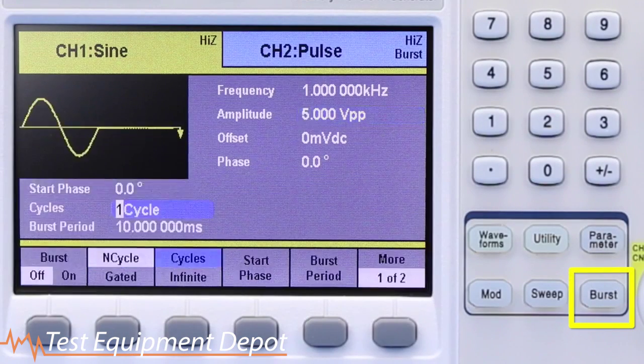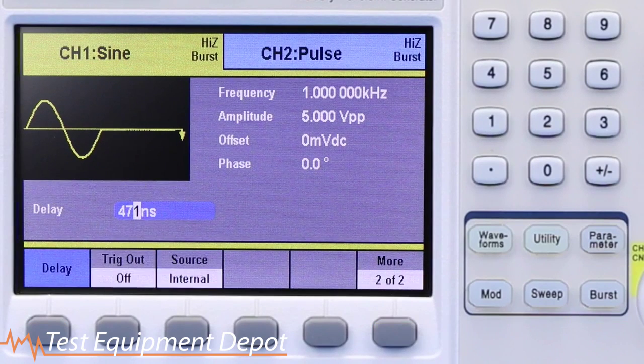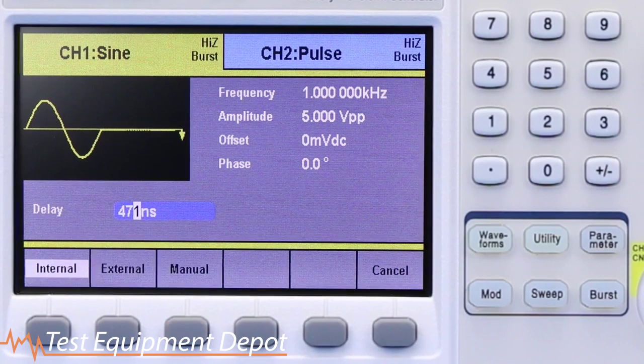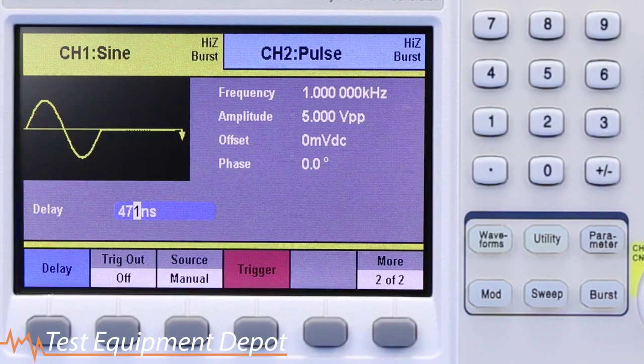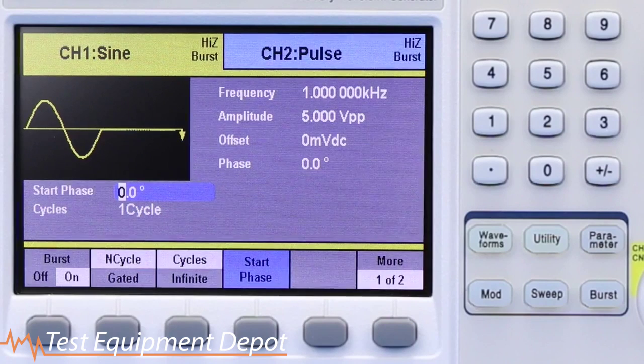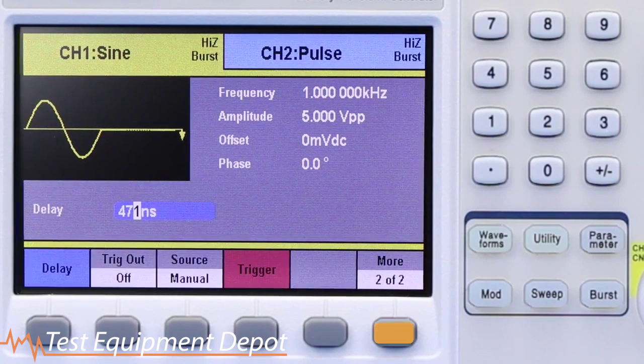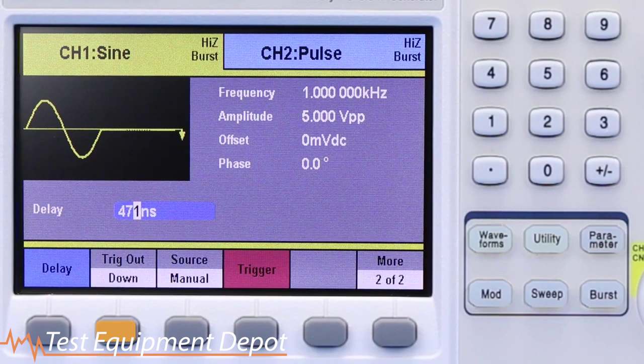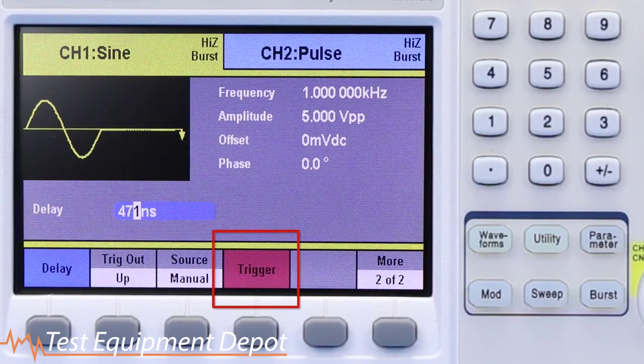On unit 1, press the burst button to enter the burst menu. Select source and choose manual. This will allow the user to trigger the burst via the front panel. Select start phase to set the phase of the waveform where the burst will begin. The trig out option will be available in the menu, allowing you to generate an external trigger signal from the unit when you press the manual trigger button.